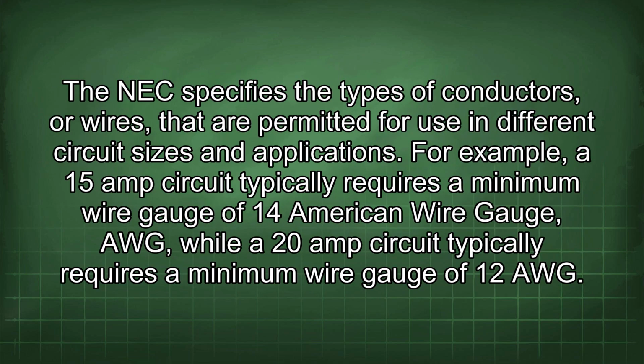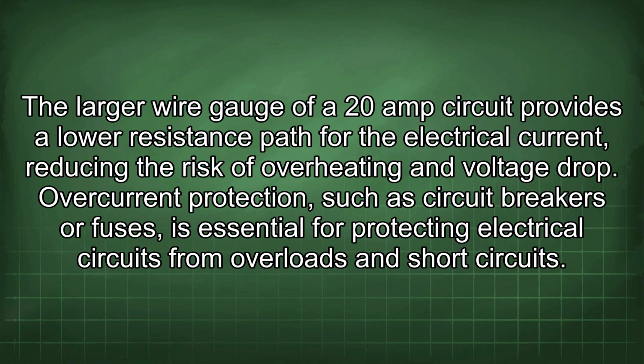The NEC specifies the types of conductors, or wires, that are permitted for use in different circuit sizes and applications. For example, a 15-amp circuit typically requires a minimum wire gauge of 14 American wire gauge (AWG), while a 20-amp circuit typically requires a minimum wire gauge of 12 AWG. The larger wire gauge of a 20-amp circuit provides a lower resistance path for the electrical current, reducing the risk of overheating and voltage drop.